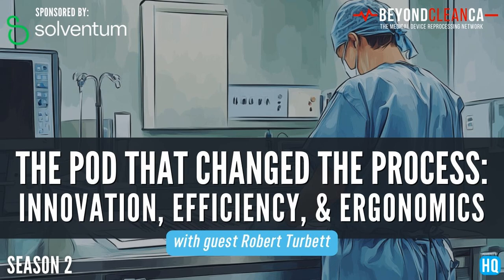As we've gone outside the world of orthopedics, because this is pretty narrow, tiny stuff, we found there are other people that have a need for this. So it's important that we look at the tools going into the device and make sure that we don't exceed those guidelines, because we haven't proven it to anything smaller than that. But other than maybe some really tiny Frazier tips, I'm not sure that I've seen anything much smaller than this. There are very complex instruments, but we don't change the process. You still have to go through the same cleaning, the same inspection process. But if it's able to go in a pre-vac steam sterilization cycle, then our device will work for that.